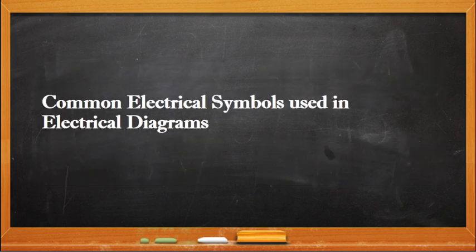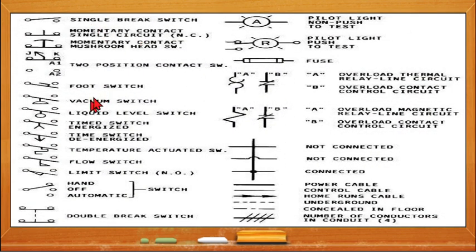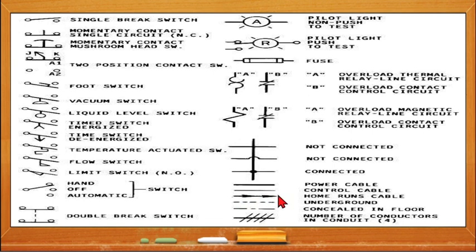These are the common electrical symbols used in electrical diagrams. We have the symbol for a single pole switch and the float switch. For indicators, we have the pilot light. We also have the fuse, overload relays, and wiring symbols — if wires are just crossing without a dot, they are not connected; if there is a dot, those wires are connected or spliced together. Then the power cable is represented by a thicker line, and the control cable by a thinner line. The home run is shown as a line with arrows, and a dashed line means underground or embedded in the ground.